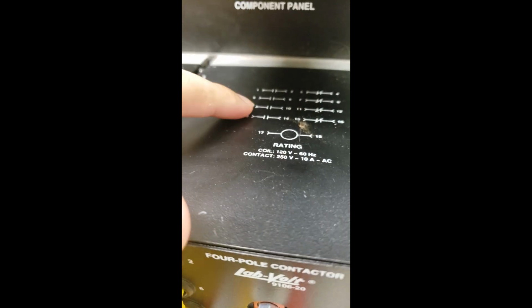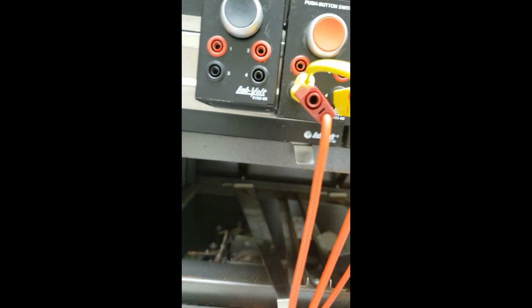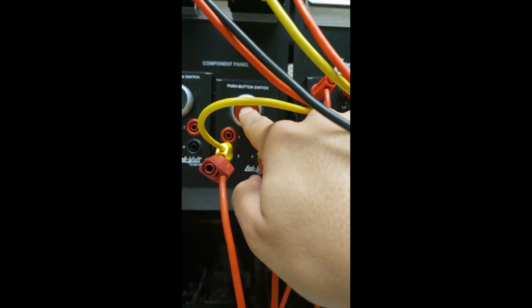This is the contactor. This is 13, 14, normally open contact, of the contactor. It will go directly in parallel to the 3 and 4 of the start push button. So now, if I press the start push button, the motor will start running. If I release my finger, nothing will happen. The motor is still running, and this one is still energized, and the lamp is still on. Now, how can I stop my motor? The only way to stop my motor is by disconnecting the circuit breaker here, which is this one. So this is the only way I can stop the motor.